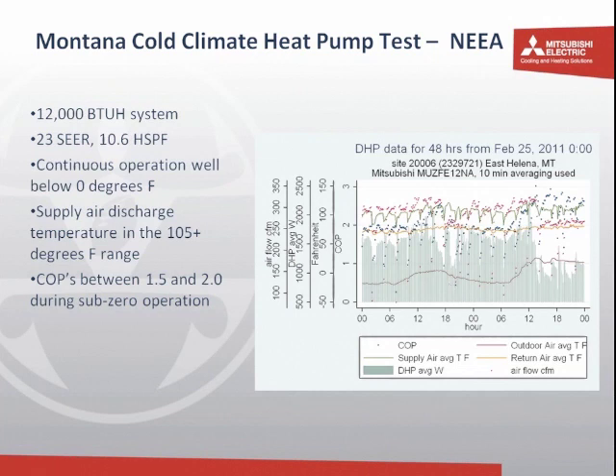So what that's telling us is even when the system is operating at a negative 25 degree temperature outdoors, it's putting out between 1.5 and 2 times the amount of heat that you would get from a conventional strip heater or resistance heater. So twice as efficient as a conventional system, even in these extremely low ambient conditions. Under normal operating conditions, these systems are 3 to 4 times as efficient as an electric resistance heater, with COPs in the 3 to 4 range. So it's a solution that's available for us even in northern climates, again, something that you wouldn't ordinarily think of a heat pump being.